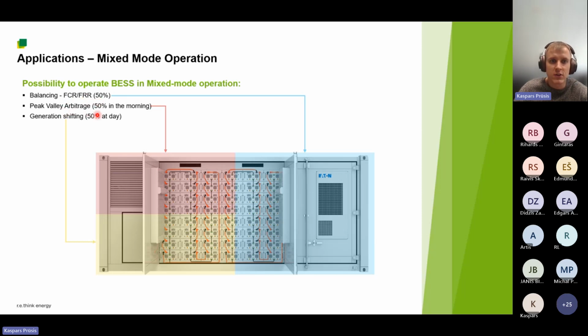Then the remaining 50% we can use for peak valley arbitrage, where in the night we charge the battery when the electricity price is low and discharge the battery in the morning when the electricity price is higher. And in the day, for example, if we have a PV plant, we can store some of the PV power in the battery and then release it into the grid later when it is more convenient and the electricity price is better. So there are multiple application scenarios that we can have, as well as mixed mode applications, which can probably give the best return on investment for your solution.